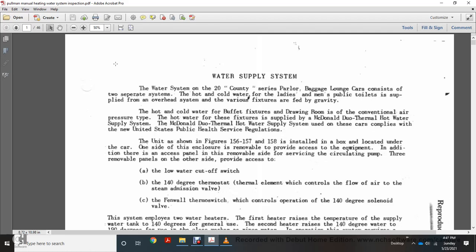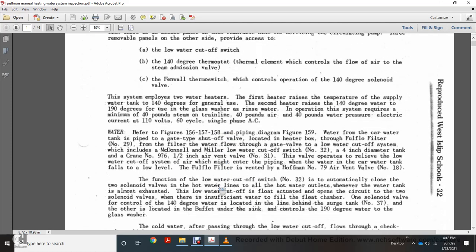Figures 156, 157, and 158 show the equipment located within the car. The system includes a circulating pump, low water cutoff switch, 140-degree thermostat, steam admission valve, and thermal controls operating at 140 degrees. The system employs two water heaters: the first heater raises water temperature to 140 degrees; the second heater raises 140-degree water to 190 degrees for the glass washer. Operation requires a minimum 40 pounds of steam, 40 pounds of air pressure, 40 pounds of water pressure, and 110-volt 60-cycle AC electrical current.